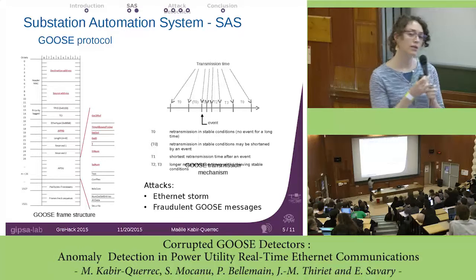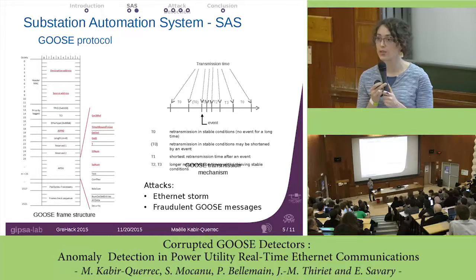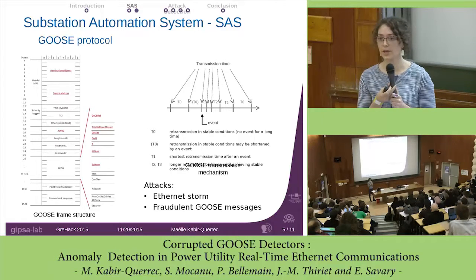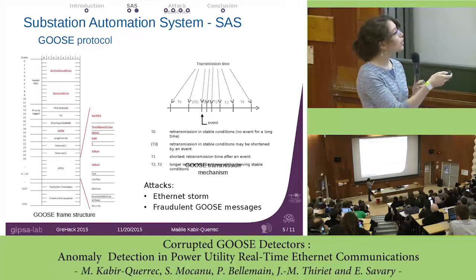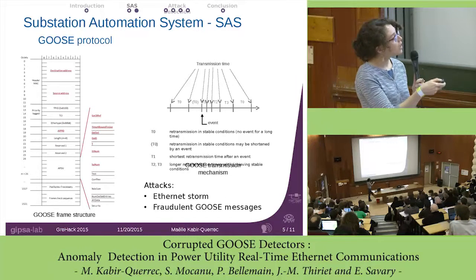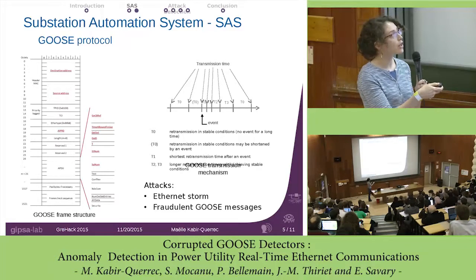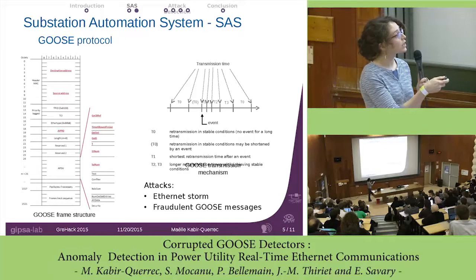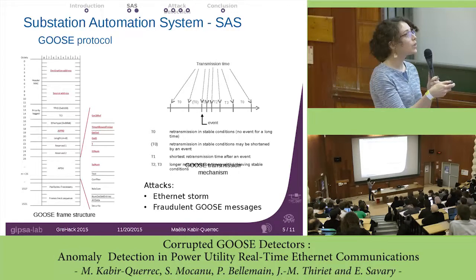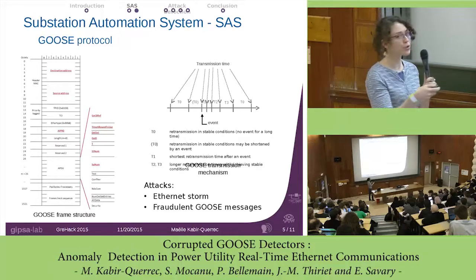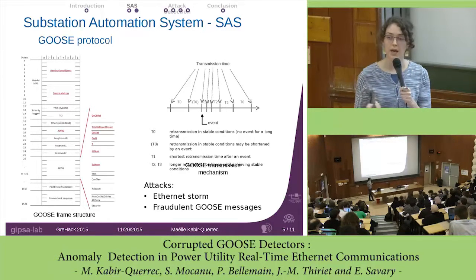GOOSE is a multicast protocol, meaning there is no acknowledgement of reception. To make the protocol more reliable, there is a specific transmission mechanism. When a data value changes, a new GOOSE message is sent — this is what I call an event. First it will be sent at a very high frequency T1, then this frequency is divided by two, going at a slower pace T2 and then T3, until stable conditions are reached and a normal pace T0 is maintained. These frequencies depend on your devices and can be configured.